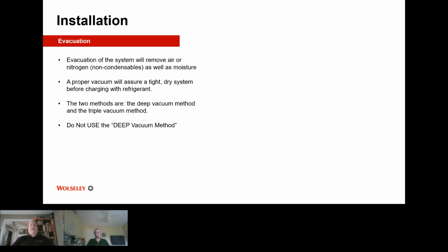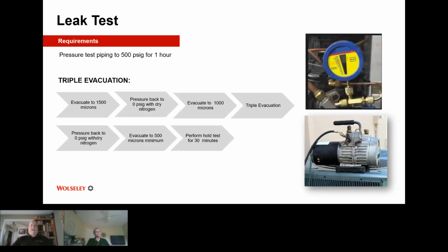And the evacuation method that is most preferred for most brands is what we call the triple evac method. The triple evac method consists of this. We are evacuating, first of all, down to 1,500 microns. And then once we reach 1,500 microns, we will stop the evac process and pressure the line set back up to 0, because when we've evacuated, it will go below 0. Once it's at 0, we are going to stop the nitrogen in, and we are going to restart the evac and go down now to 1,000 microns.